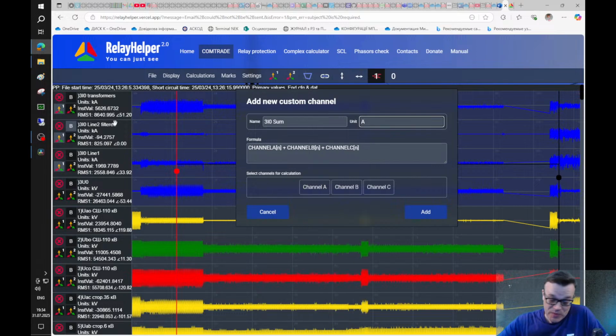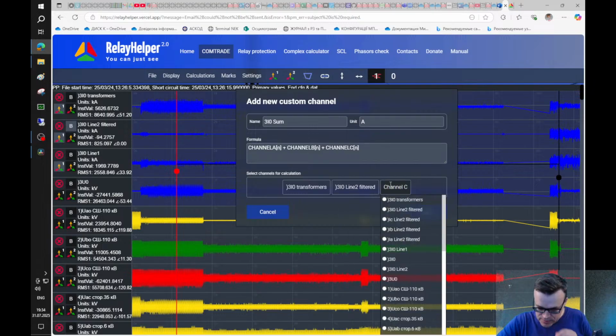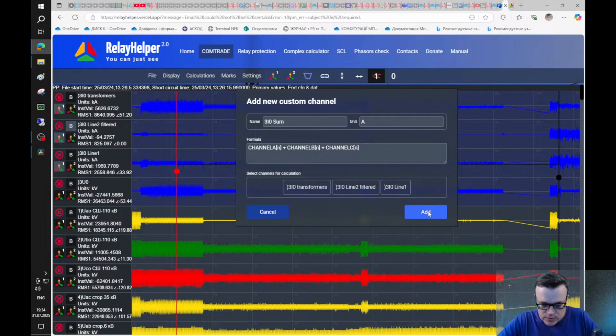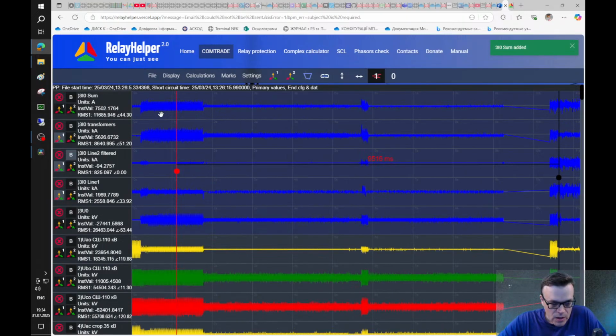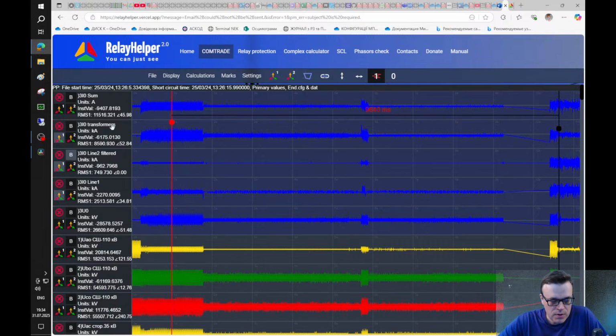No, I don't need to remove the third one. Okay, I put amperes here, so the channel with the calculated sum will be correct. Sorry, shit happens. So I add the transformer zero sequence current, filtered, from line 2, and zero sequence current from line 1. Okay, we have 11 kiloamperes current.